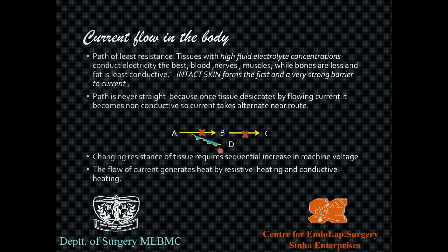The changing resistance of tissue. Now, when this becomes desiccated, it is not passing any current. So temporarily, what is the machine trying to do? The machine is trying to force more current. So what is it doing? The machine voltage increases sequentially by itself. But once it sees that it's not able to do so, then the current takes an alternative route. Now, when the machine voltage is increasing, it becomes more damaging, right?